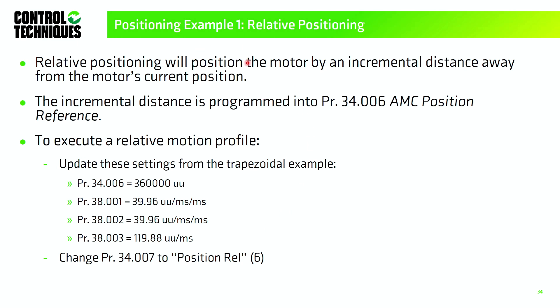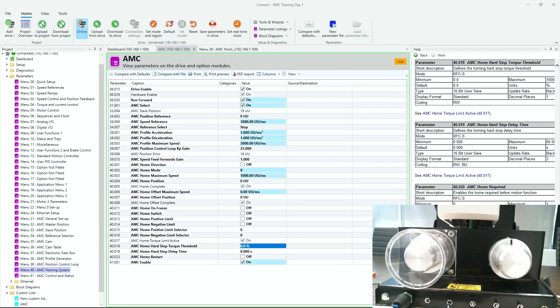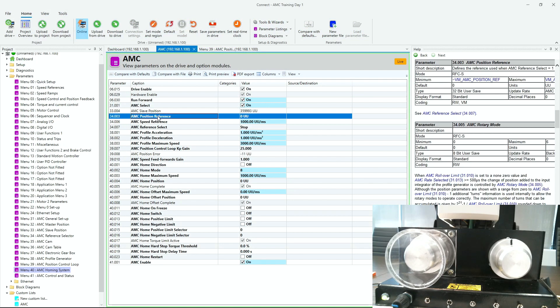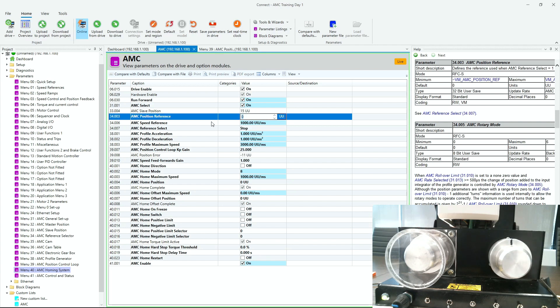To execute a relative motion profile, set menu 38-03 (speed) to 119.88 UU/ms, and menu 38-01 and 38-02 (accel/decel) to 39.96 UU/ms². The position reference in menu 34 is set to 360,000 user units (one motor revolution). Then change menu 34-07 from stop to position relative to execute the profile.